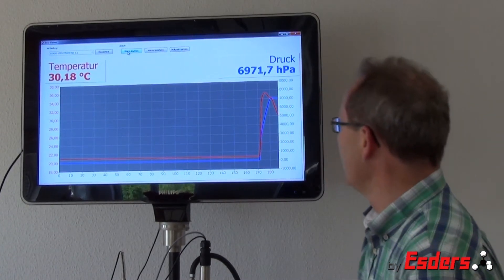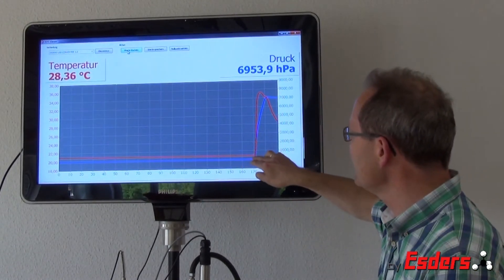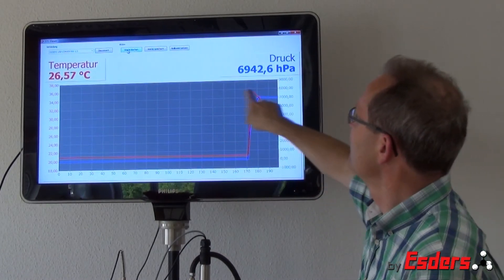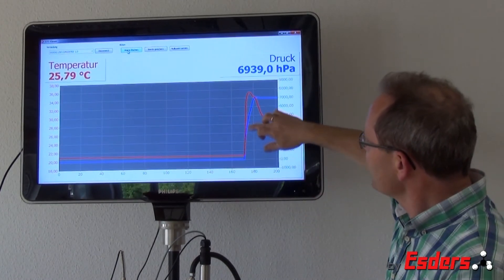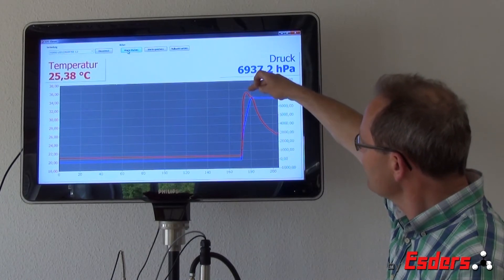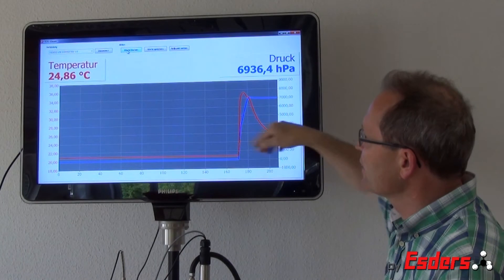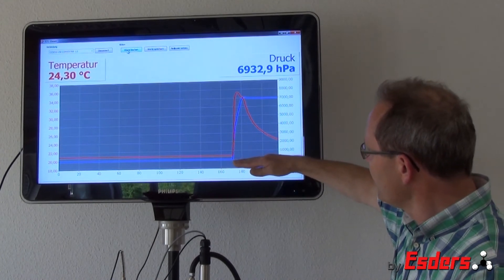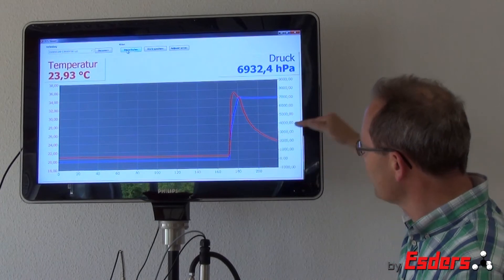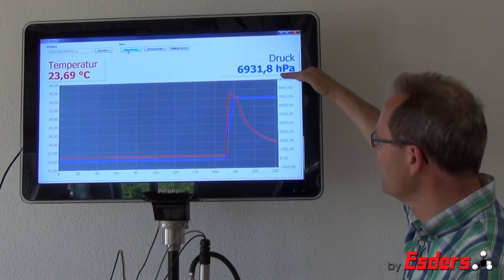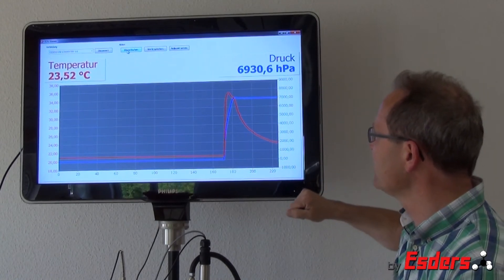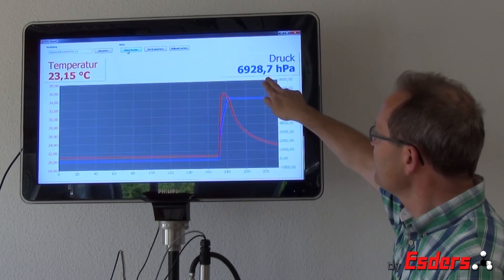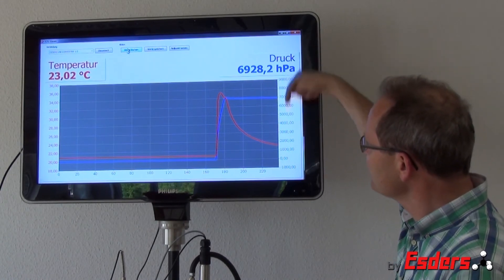I switch off the compressor and what we can see is that the temperature immediately rises from about 21 degrees to about 35 degrees centigrade. At the same time the pressure rises, and here we see that the temperature has already decreased and fallen back to 25 degrees centigrade. The figure here gives us immediately the information that the pressure is still falling down.